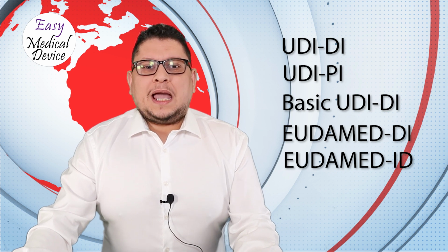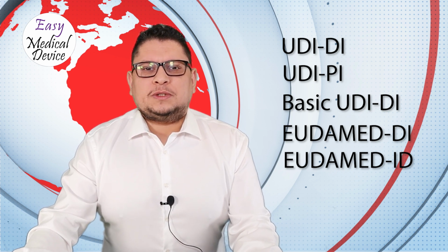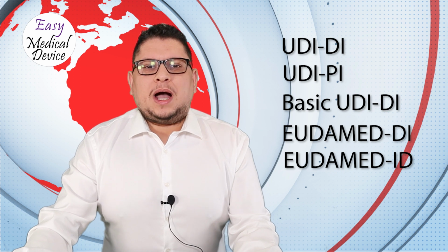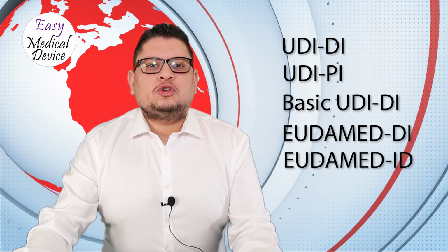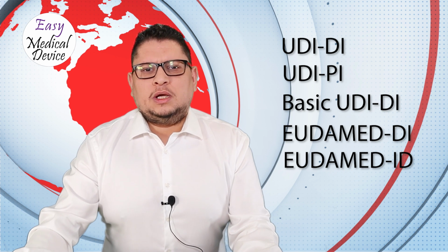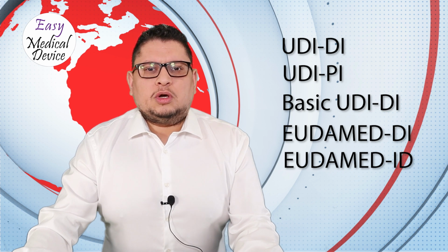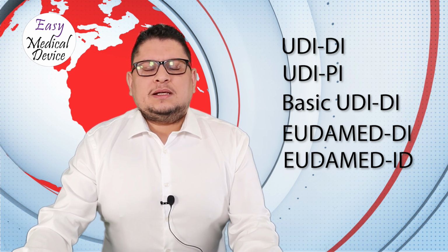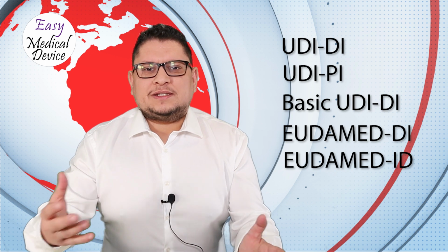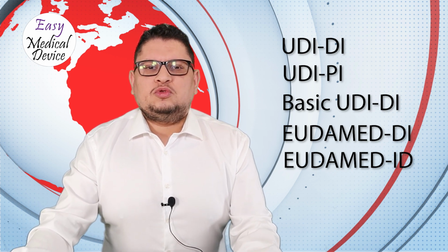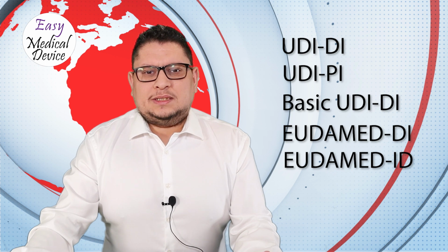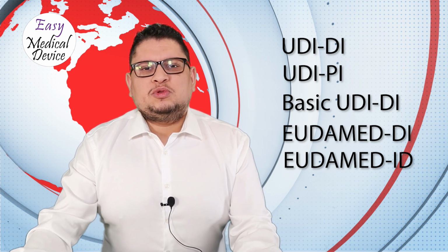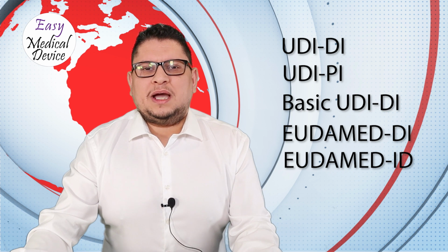The guidance provides you some information about registering your legacy devices on EUDAMED. For example, if you already have a UDI DI because maybe you are selling your products in the USA, because the USA already has a UDI DI rule, then you can still use this UDI DI to create, if I can say, the elements for the registration on EUDAMED. If you don't have a UDI DI, then the EUDAMED database will create this code by itself.